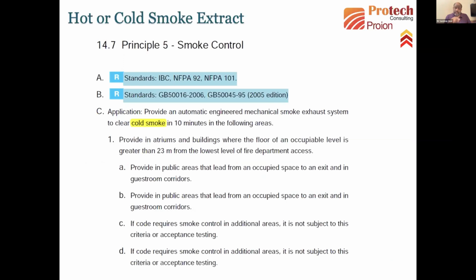Once the fire is extinguished - this is very clearly written in the British standards - then you remove the smoke. The smoke in suspension is to be removed. But if you think doing 12 ACPH lets you keep a group of people in that space through exhaust systems creating tenability, the answer is no. The systems are provided for cold smoke extract after the fire is extinguished.